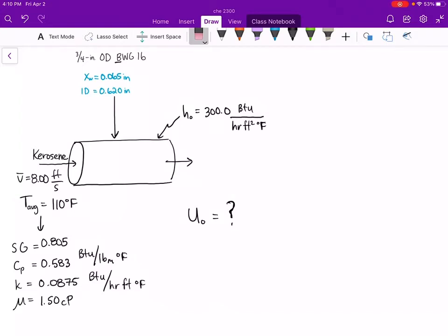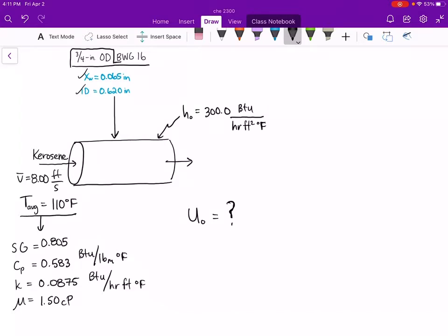We are told that the tubing or piping material is three-fourths inch outside diameter BWG 16 piping. Based on this, we know that the outside diameter is 0.75 inches. From the back of the textbook we can get the thickness of the pipe as well as the inside diameter of the pipe. We are also told that the convective heat transfer coefficient on the outside of the pipe is 300 BTUs per hour foot squared degrees Fahrenheit. Since our kerosene is at an average temperature of 110 degrees Fahrenheit, that is the bulk temperature of our fluid, and we can look up fluid properties at that temperature.